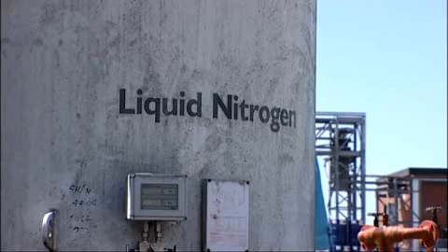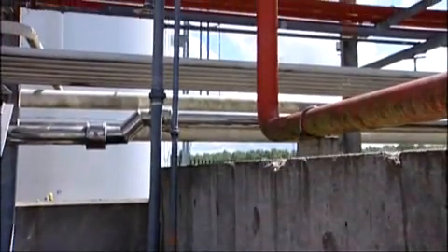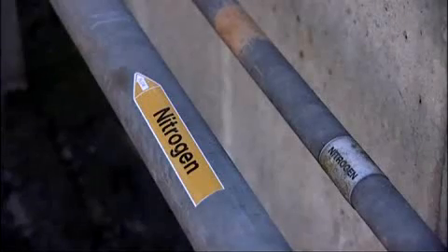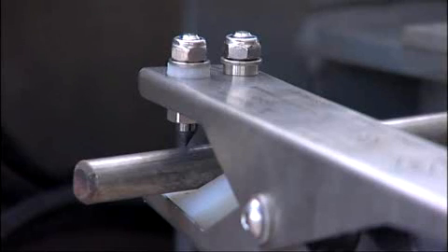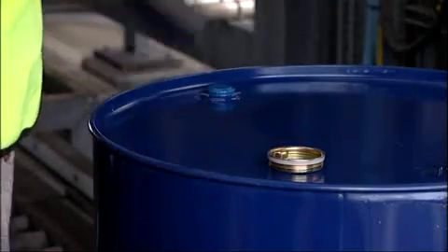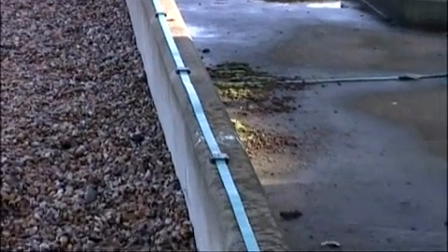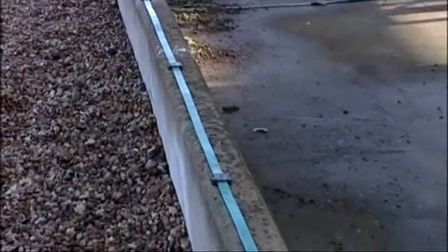Where it is not possible to reduce the buildup of electrostatic charge to a safe level, inert gas blanketing should be considered both for vessels and pipes. Earthing and bonding is a very effective technique for minimizing the likelihood of an ignition from static electricity, and is particularly important where the end user of solvents cannot avoid the generation of static electricity due to the nature of the process, such as a spray application.